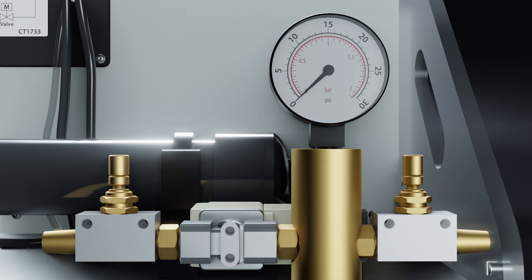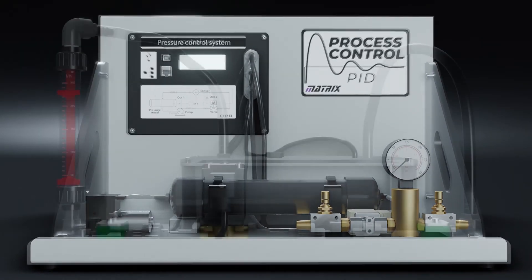The vessel pressure is measured by a Bourdon type mechanical gauge along with a pressure sensor. The Bourdon gauge provides a visual indication of the pressure in the vessel and a means for students to check and calibrate the controller input from the pressure sensor.